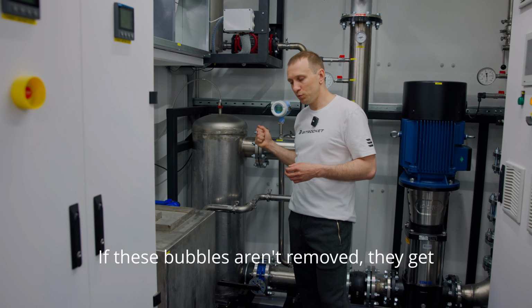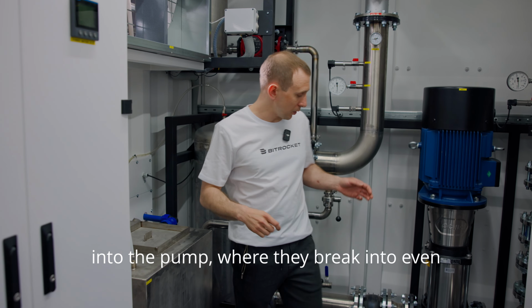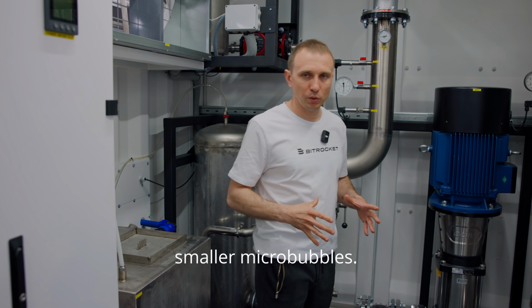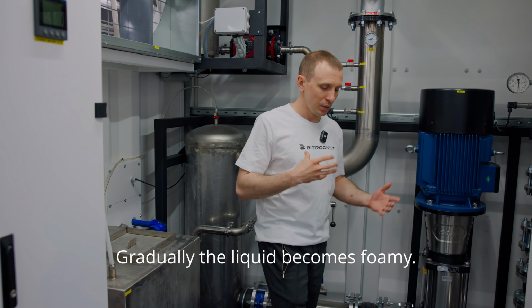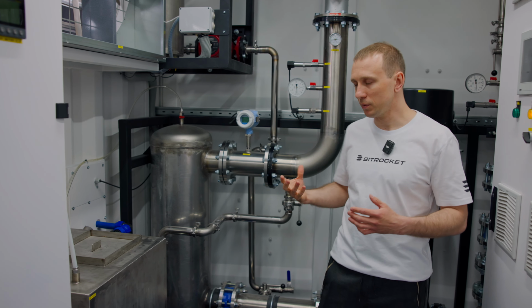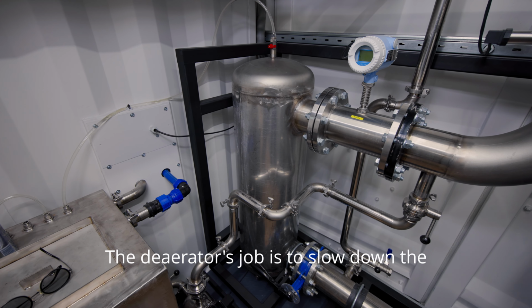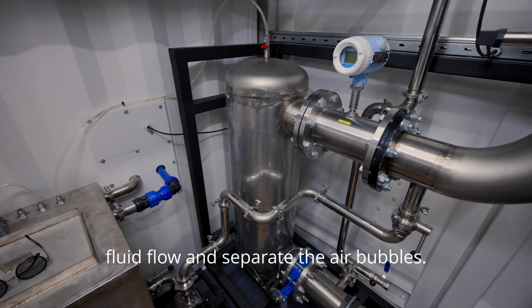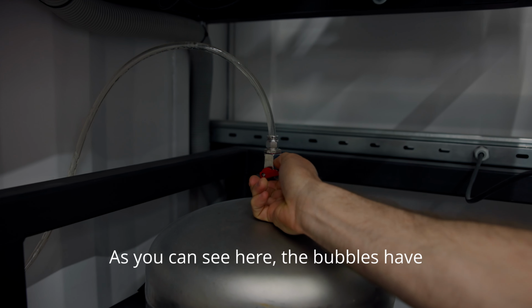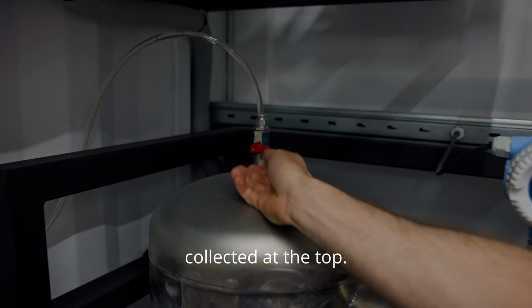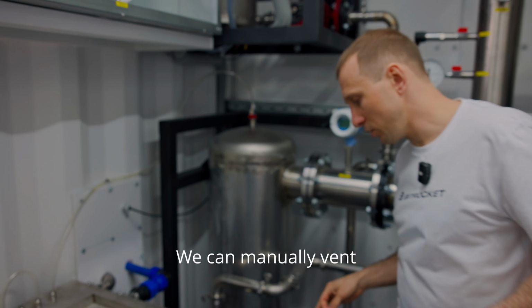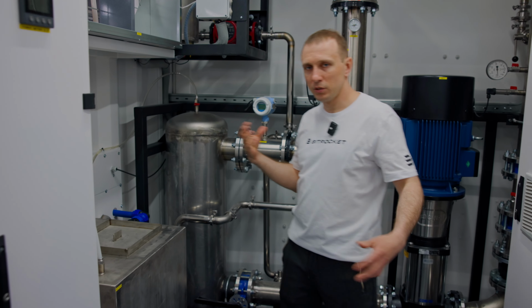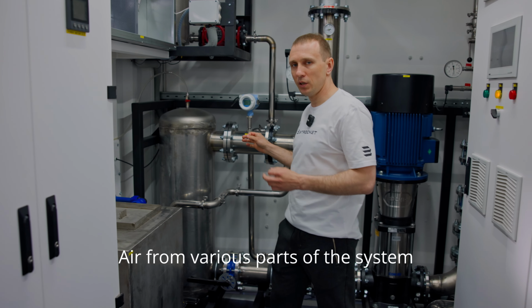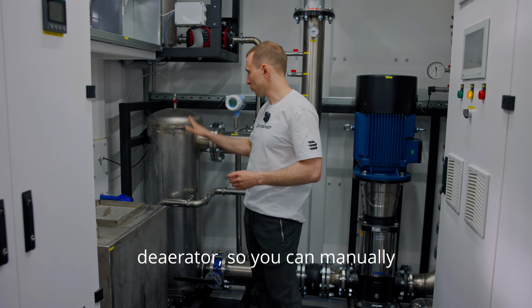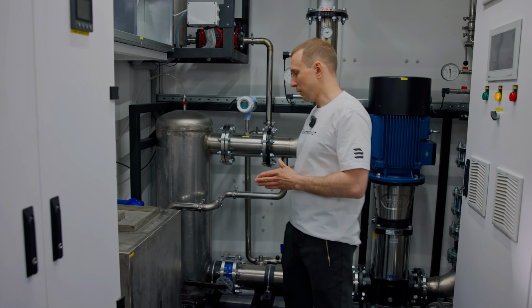If these bubbles aren't removed, they get into the pump, where they break into even smaller micro bubbles. Gradually, the liquid becomes foamy. The deaerator's job is to slow down the fluid flow and separate the air bubbles. As you can see here, the bubbles have collected at the top. We can manually vent them from time to time. Air from various parts of the system gradually accumulates in the deaerator, so you can manually remove it.